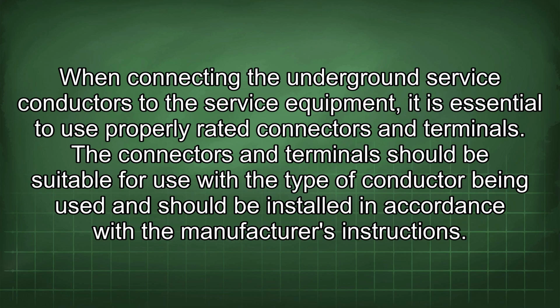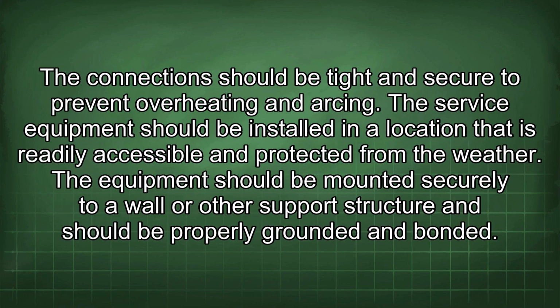The connectors and terminals should be suitable for use with the type of conductor being used and should be installed in accordance with the manufacturer's instructions. The connections should be tight and secure to prevent overheating and arcing. The service equipment should be installed in a location that is readily accessible and protected from the weather. The equipment should be mounted securely to a wall or other support structure and should be properly grounded and bonded.